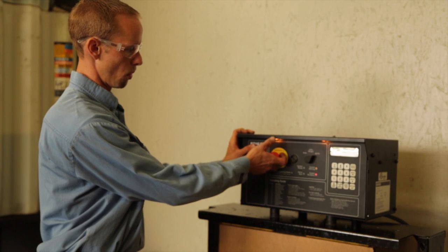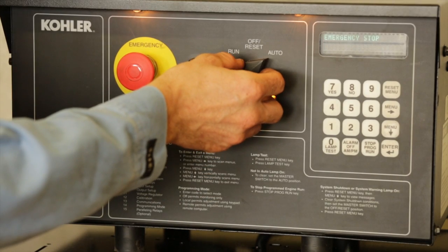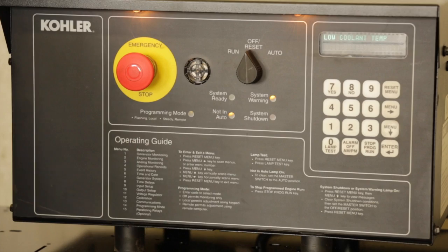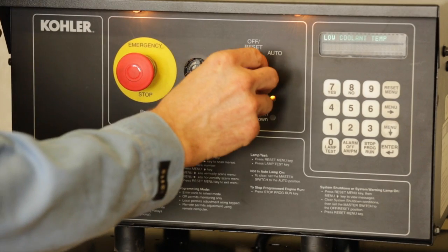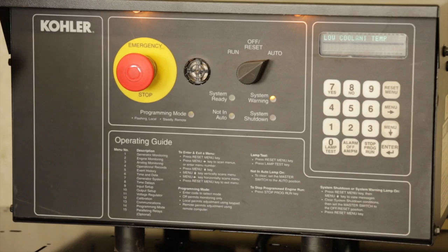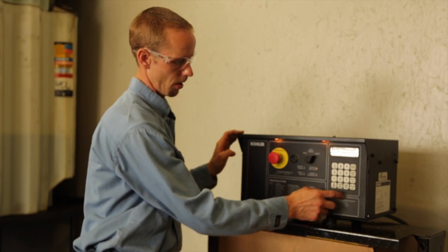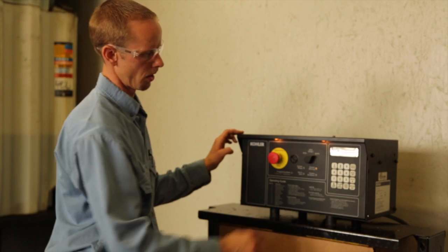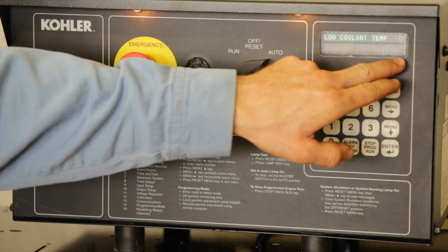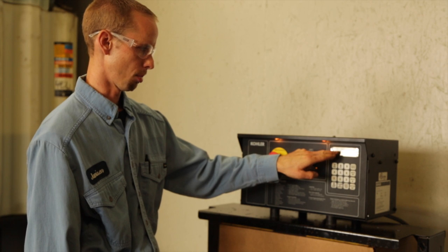To reset a fault — in this case emergency stop — pull out the e-stop and turn the controller switch to the off reset position, then move it back to the auto position. Press the alarm off button to reset the faults. The buttons on the side of the controller control the functions. Currently a low temperature alarm is displayed, but if the unit were in auto, the display would say system ready.